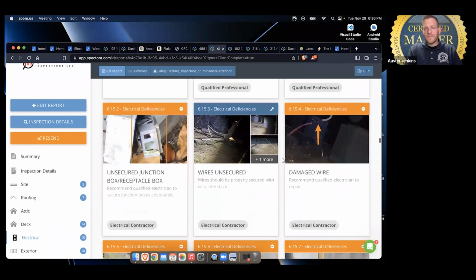Going into the crawl space of this specific house, we had wires just draped across the ground with very few securing clips, laid out everywhere. They had taken two wires, you can see right here, and spliced them together, which ironically were both 10 gauge — a 10 gauge wire with white sheathing and a 10 gauge orange wire.